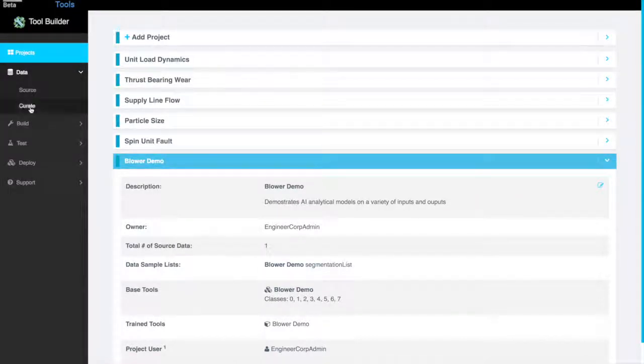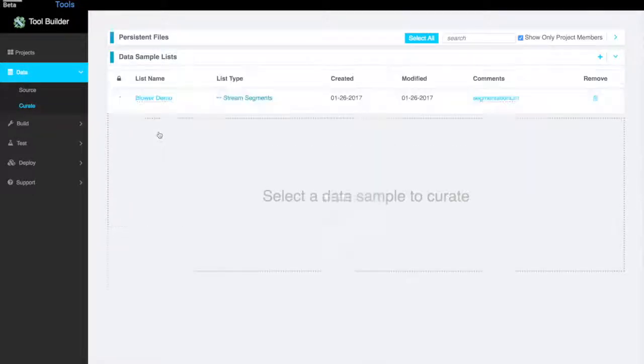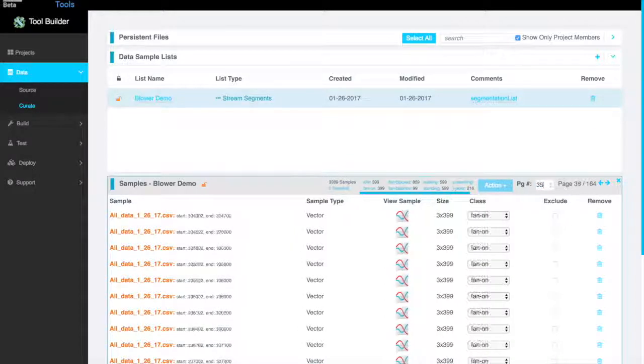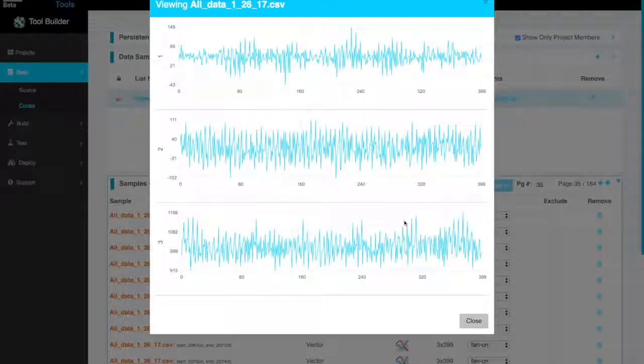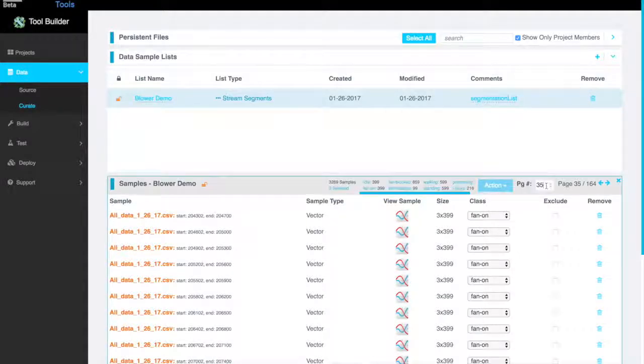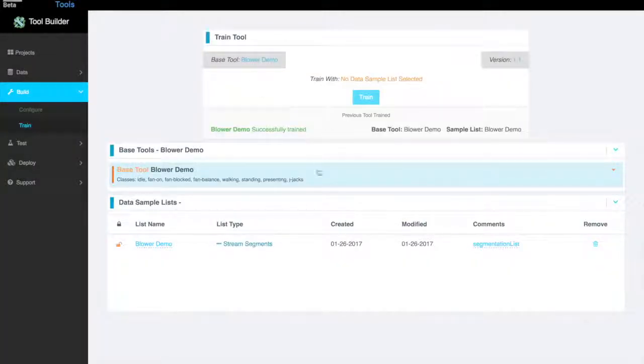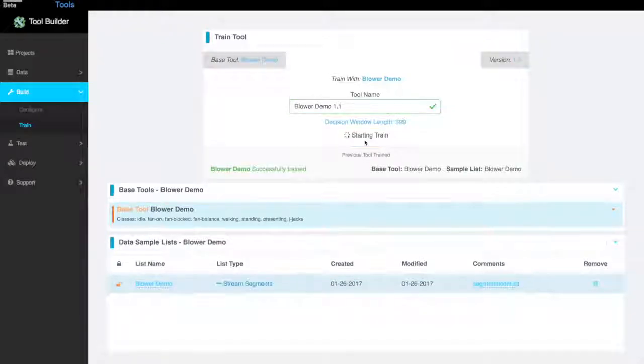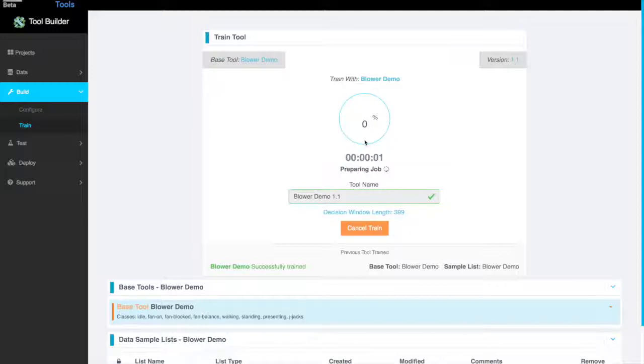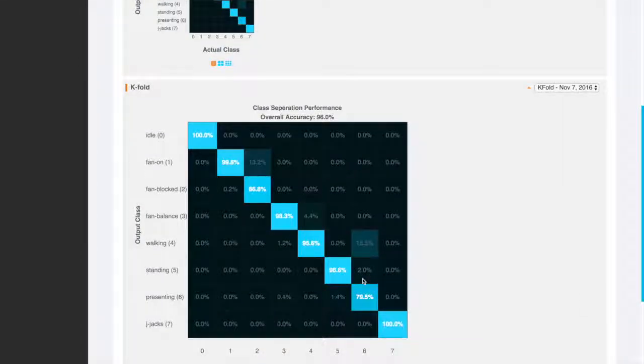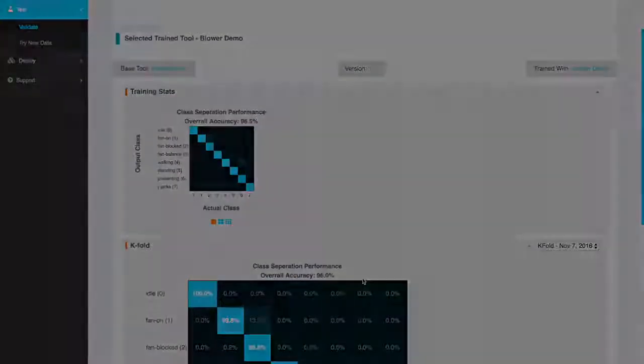Here's the software you'll use when you work with Reality AI. Like any machine learning application, it learns by example. So for the purposes of this demo, we recorded the fan operating for about two minutes in each of the several conditions that we wanted to be able to detect. Here's an example of vibrations recorded when the fan was operating normally, and here are some examples of vibrations recorded when the fan was operating with the input blocked. Once your data is loaded, it's as easy as picking a base tool configured with our help, selecting the data you want to train against, and hitting the train button. You'll also get a complete set of validation statistics, tools for helping you continually improve your classifier, and options for deploying either to the cloud or to your embedded target.